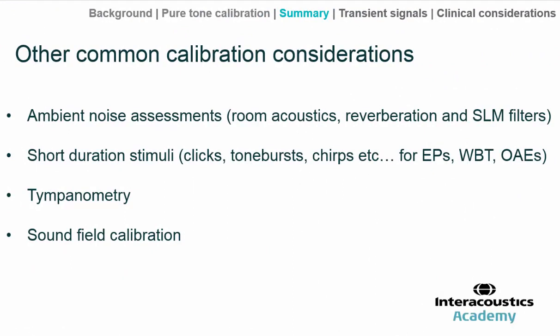Moving on, there is the consideration of ambient noise and the testing environment, particularly for sound field testing. There is a very important consideration — the correct calibration of short-duration stimuli: clicks, tone bursts, and chirps. This is important because of the extensive applications in evoked potentials, wideband tympanometry, and OAEs. It's not just audiometry we have to calibrate instruments for, but also tympanometry, which emits a pure-tone stimulus at 226 Hz, 1000 Hz, etc., and we know how to calibrate that sound.